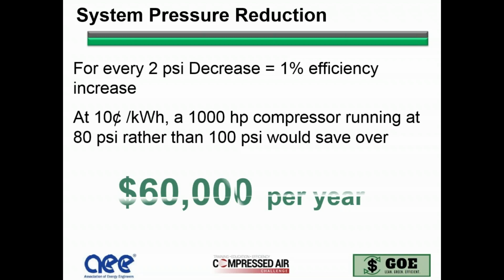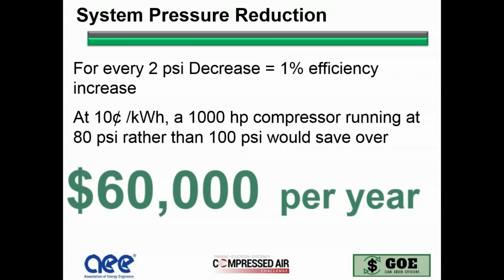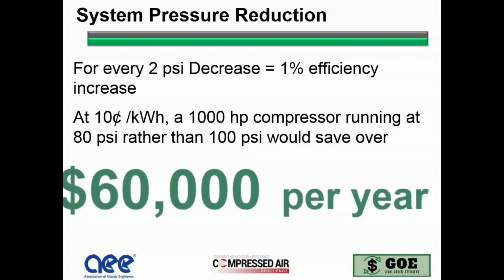So if I can reduce that 2 PSI on a 1,000 horsepower motor, running at 80 PSI rather than 100, it would save over $60,000 a year. So this is really important. You might say, well, boy, 1,000 horsepower, that's an awful big compressor. Well, I can also back it off and say it's 100 horse, and then that's $6,000 per year.